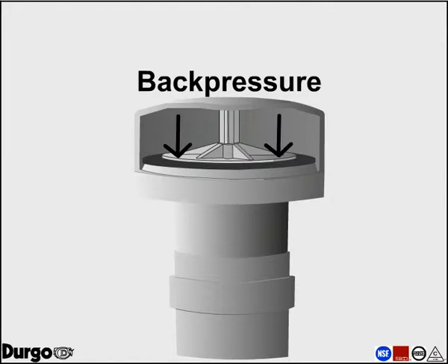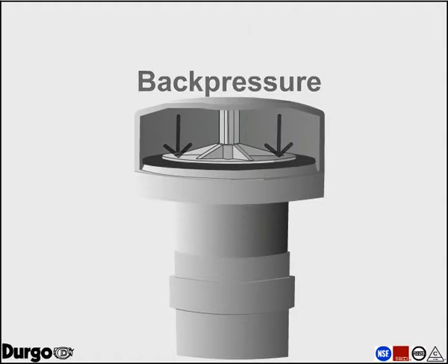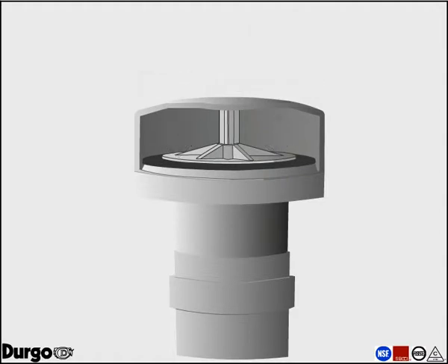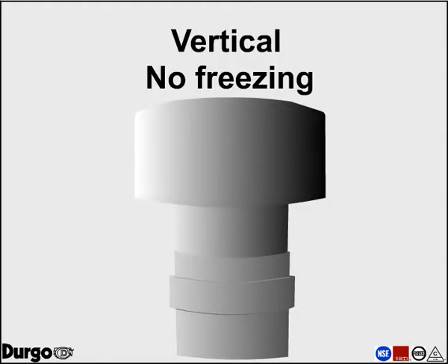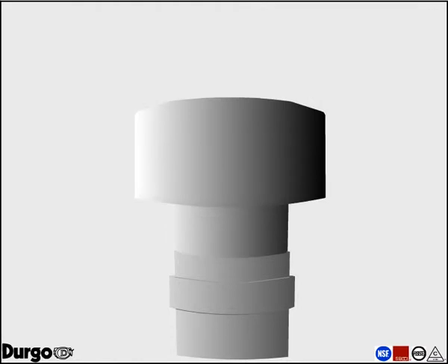In case of back pressure, the sealing element of the Durgo air admittance valve closes tightly. The Durgo air admittance valve is a non-mechanical valve that operates by gravity. It is a maintenance-free valve as long as it's installed vertically and where freezing does not occur.